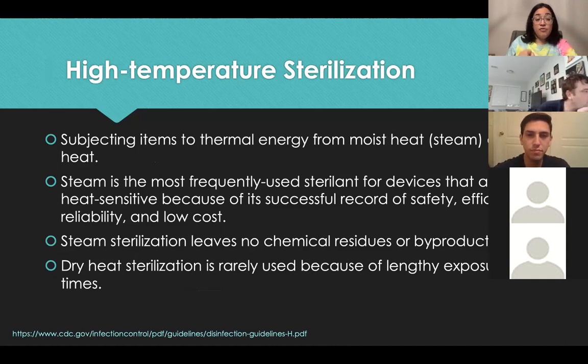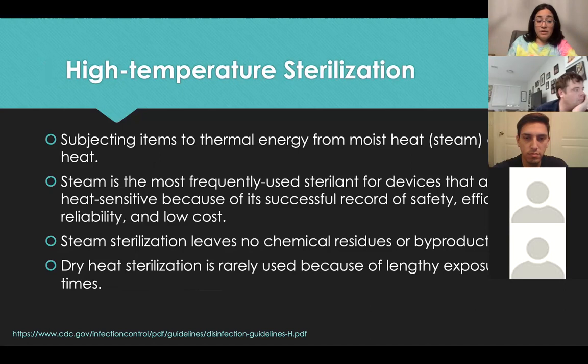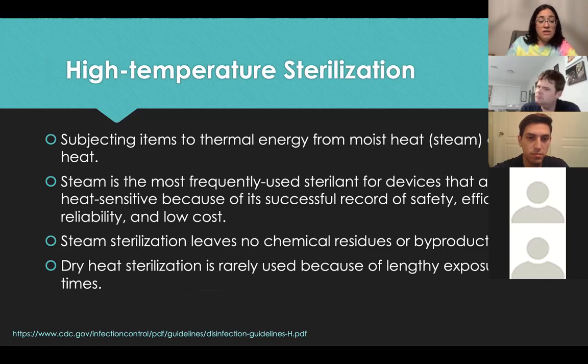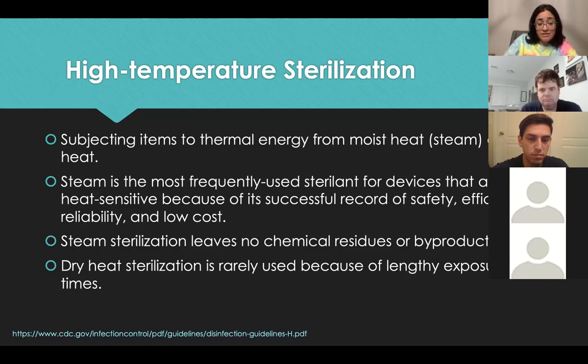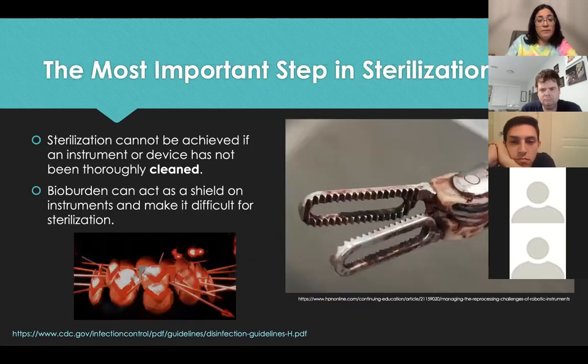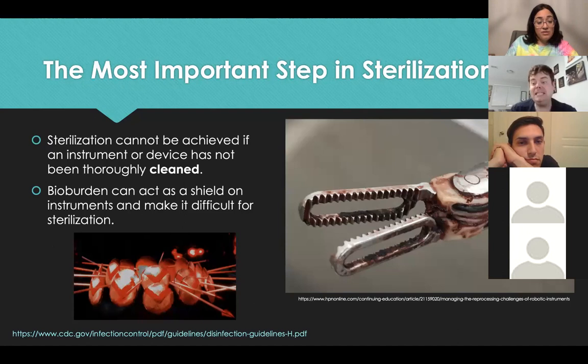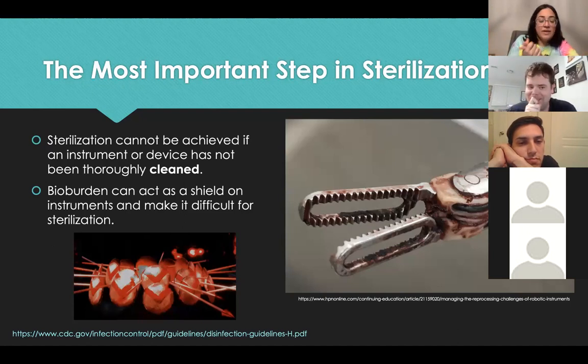High-temperature sterilization subjects items to thermal energy from moist heat or steam, or dry heat. For this discussion, we're only focusing on steam — not dry heat. Steam is the most frequently used sterilant for devices that are not heat-sensitive, because of its successful record of safety, efficacy, reliability, and low cost. Steam sterilization leaves no chemical residues or byproducts. The absolutely most important step in sterilization or high-level disinfection is cleaning — decontamination starting at the point of use.